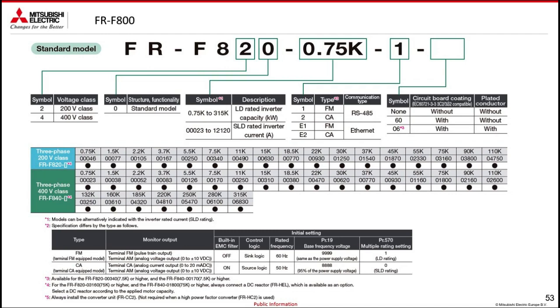The range of sizes has been greatly expanded. As regards 200 volt, it is 3-phase, as single phase is not possible on this model. Single phase connection is still possible, but there will be a derating of approximately 30% of the nominal power. The sizes are those shown below. There are also special versions of FR-F and FR-A. It is clear that they are a special version due to the fact that after the digit that indicates the power supply, there isn't the number 0, but another number.